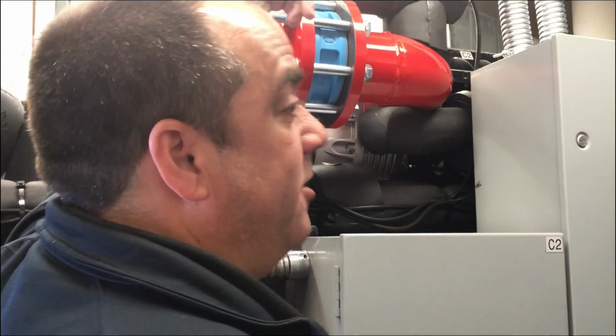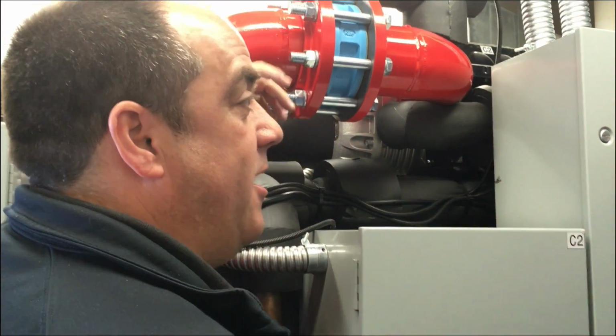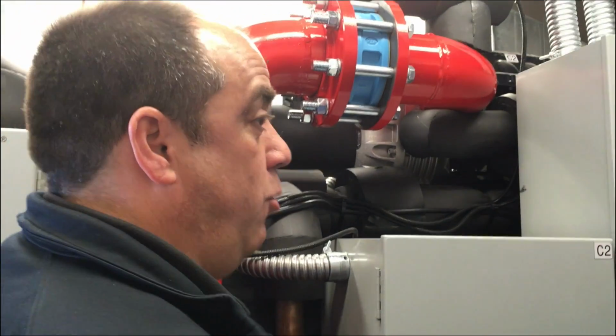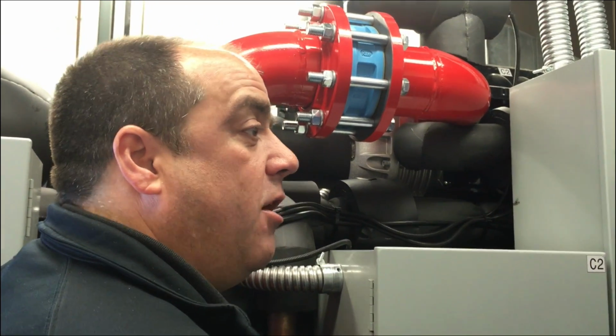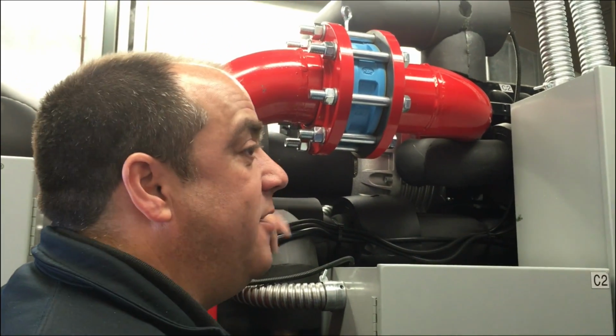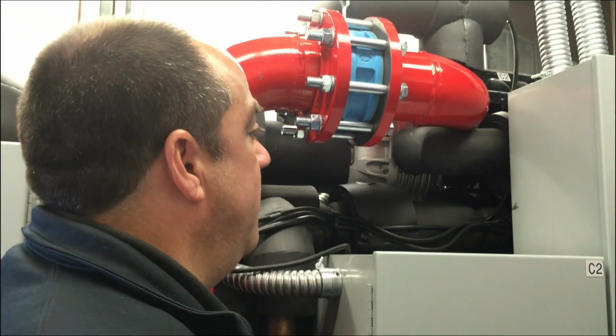So right, it just doesn't like it because we've got that magnet. We're starting at a very low speed. There's no real torque. Only about a half an amp draw at startup for this machine. So you're not going to dim the lights every time you start a compressor or anything like that.